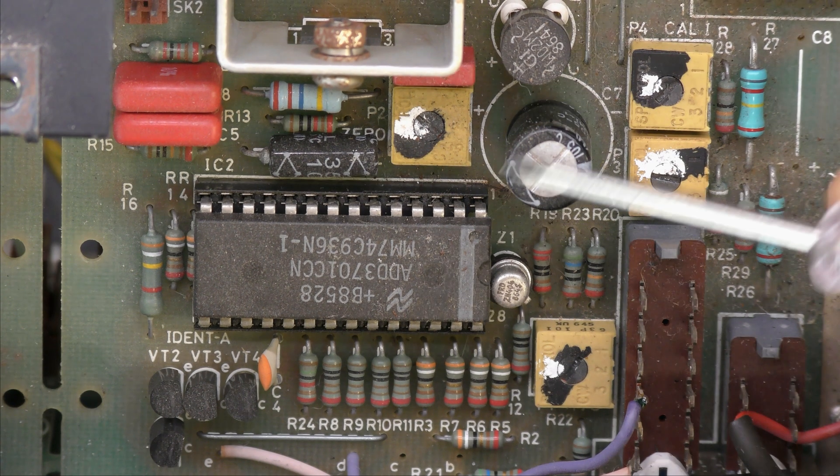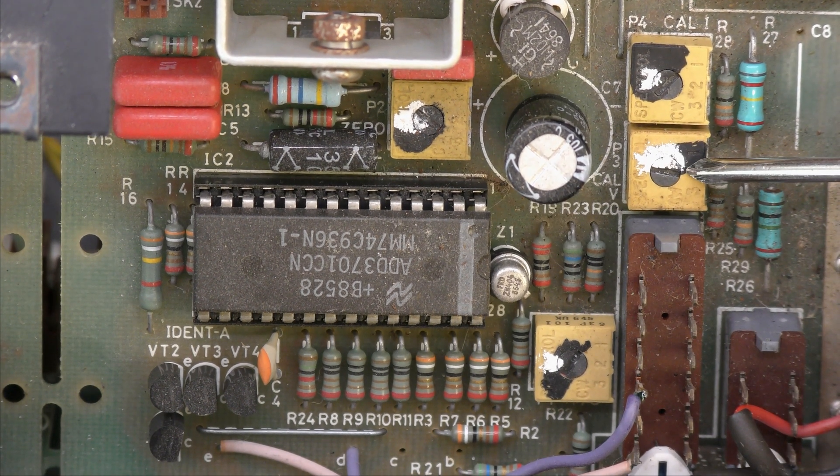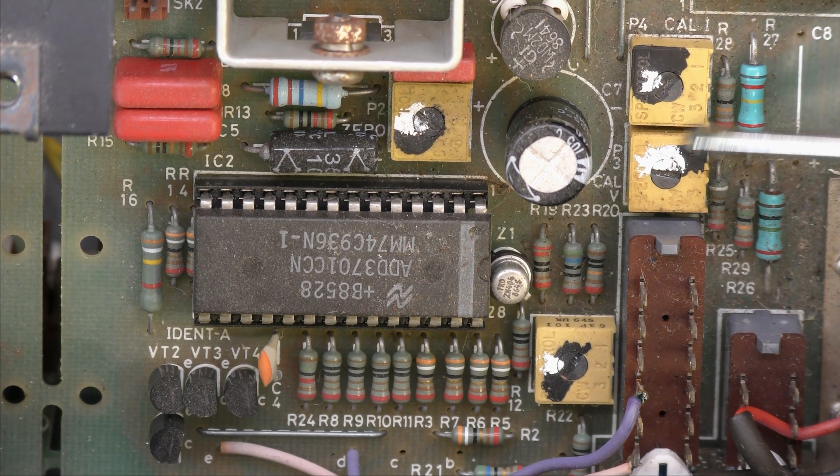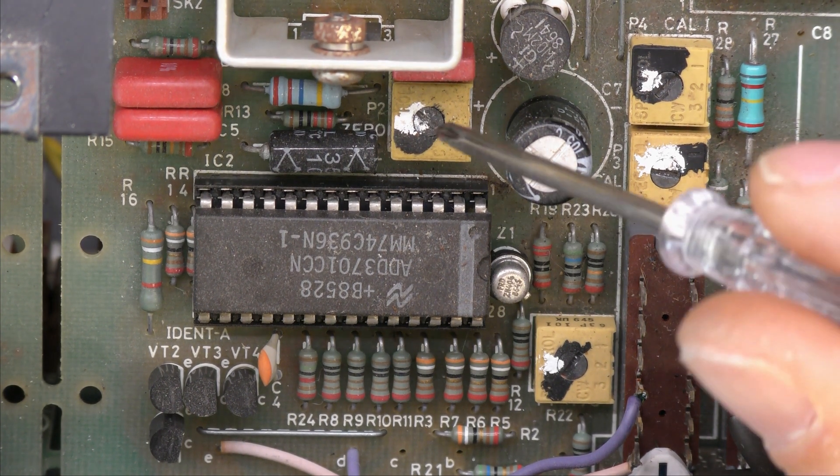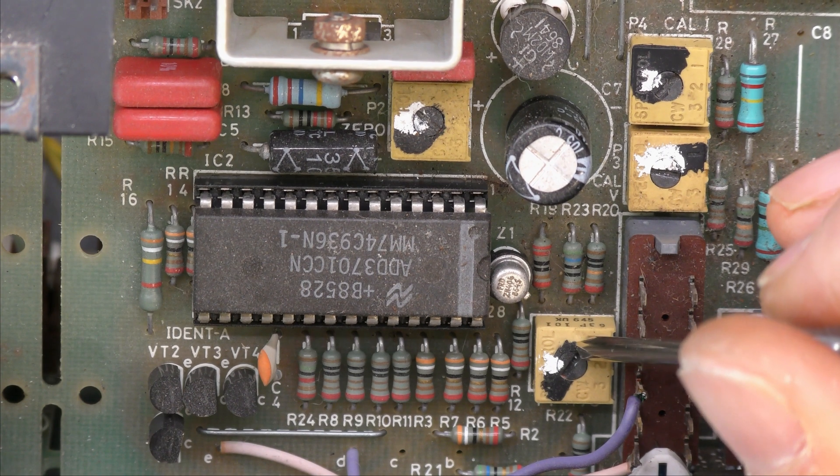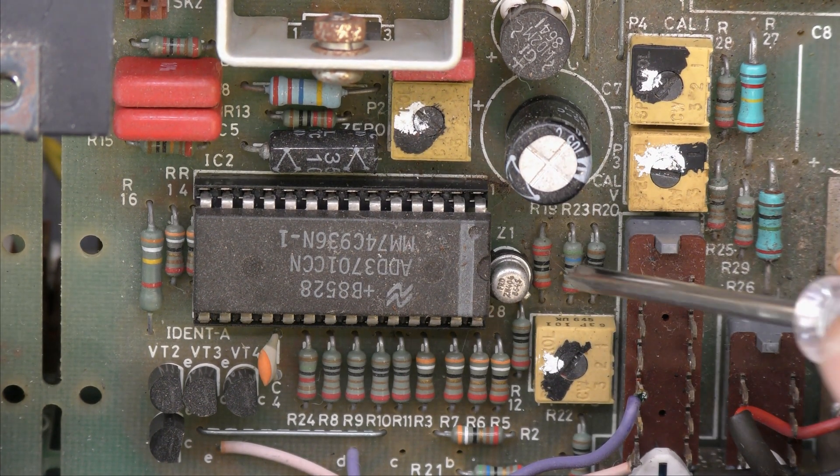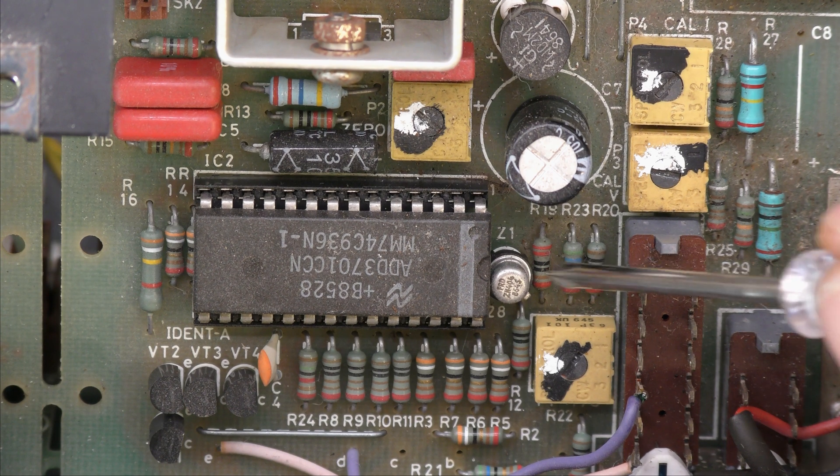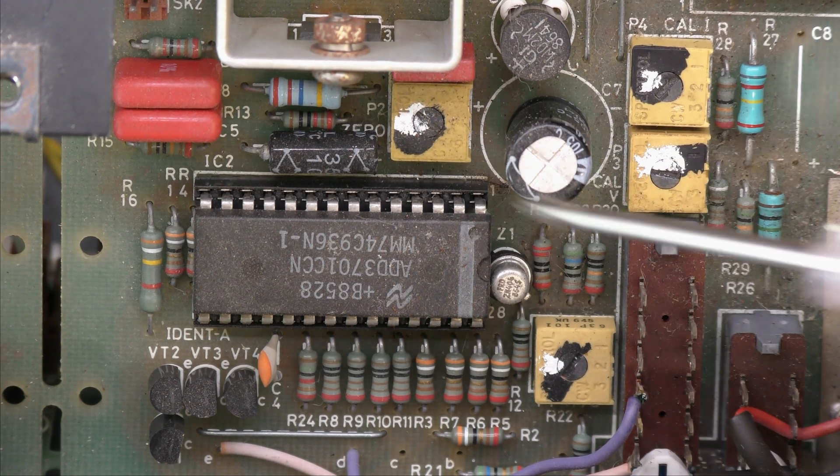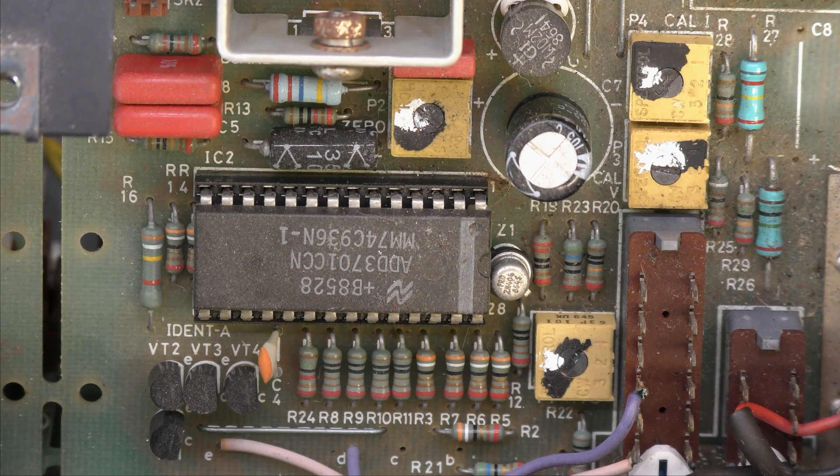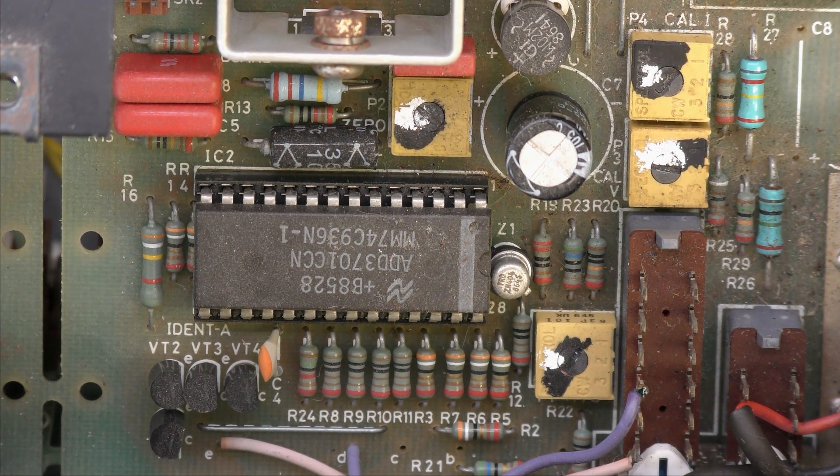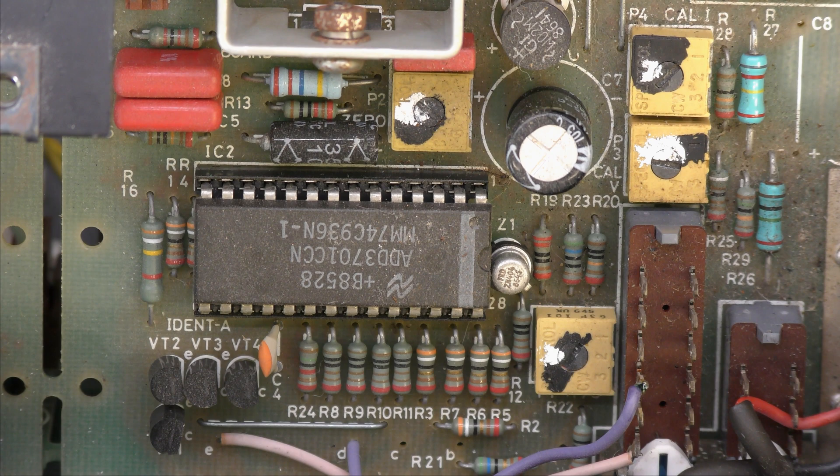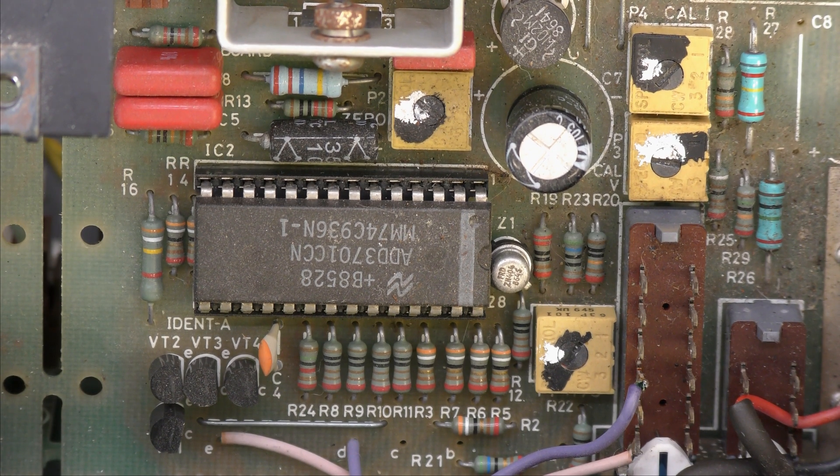On the meter board there's a calibration for the voltage reading and the current reading. Sometimes I end up tweaking those. There's also a zero and a full scale for the meter itself but you need to put separate voltage in really to set the full scale but the zero sometimes had to give a bit of a tweak too and that usually solved the problems I had where the meter was slightly offset when there was no current or voltage flowing.